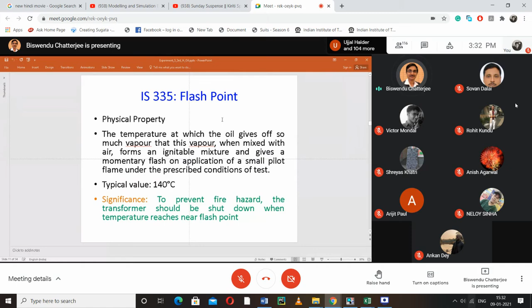This typical value is 140 degrees Celsius. What is the significance? It defines the upper limit up to which the transformer can be operated. To prevent fire hazard, the transformer should be shut down when temperature reaches near flash point. This is a safety measure. How do you measure? Each and every transformer has a temperature indicator with it, and from this indicator you will notice where the needle goes and the temperature at which the machine is operating.